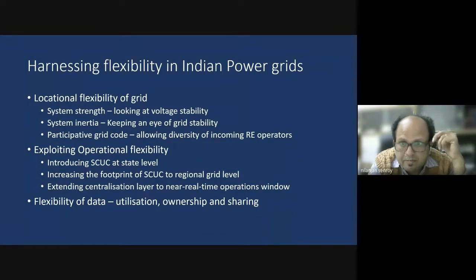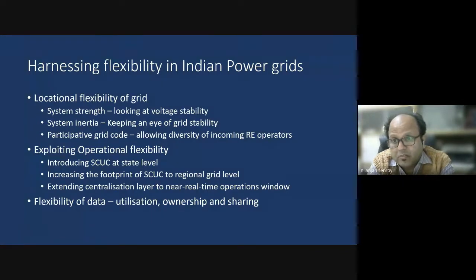Once you have identified shortfalls in available inertia, corrective actions must be taken. These can be setting up of new transmission lines, installation of synchronous condensers, identifying minimum synchronous generator dispatch in an area, as well as distributing the spinning reserves within an area in a smart way. And finally, we can always explore the deployment of virtual inertia from grid-forming converter systems.